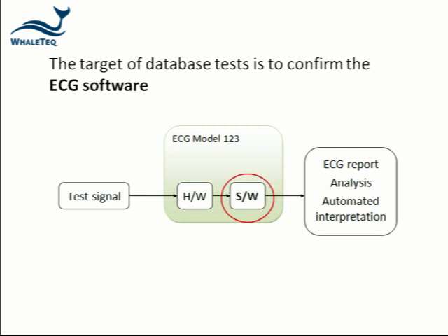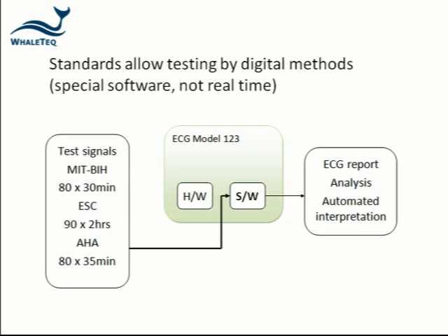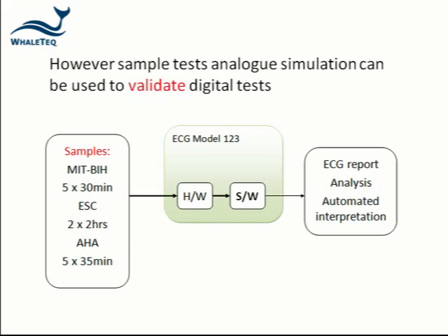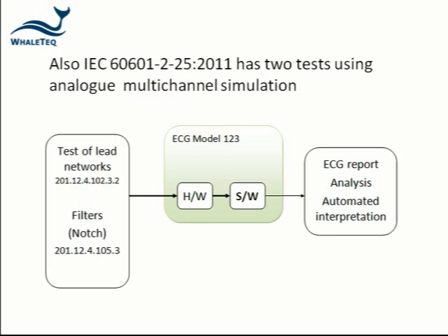These tests can take a long time to run in real time. As such, the standard allows the manufacturer to perform the test by digital simulation. However, sample tests using analog simulation can be used to validate the digital tests. This is not only good practice, but required in some standards. Also, for IEC 60601-2-25, there is a minimum of two tests that must be performed by analog simulation with a multi-channel simulator.